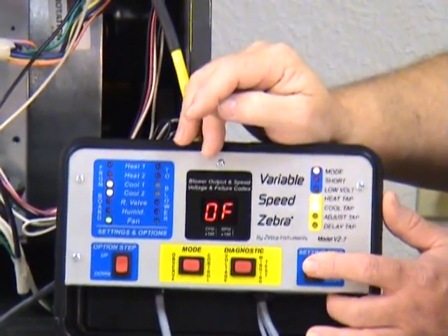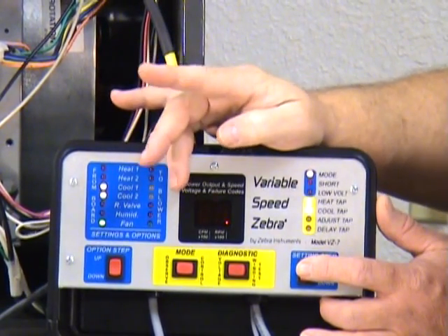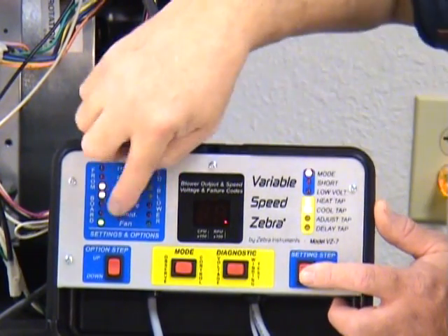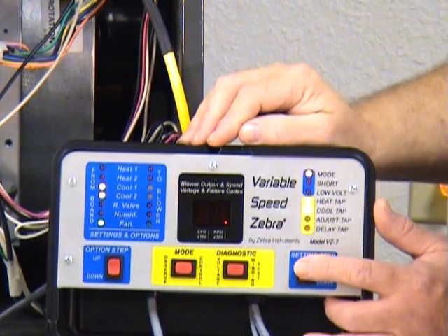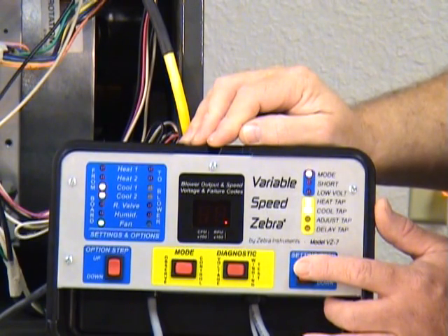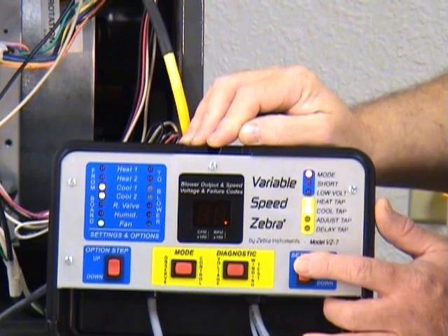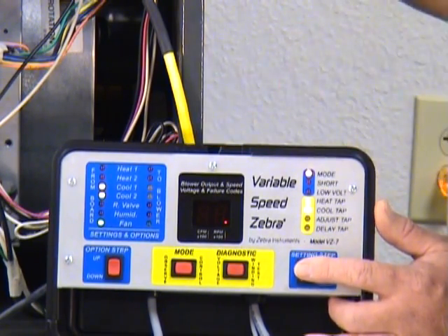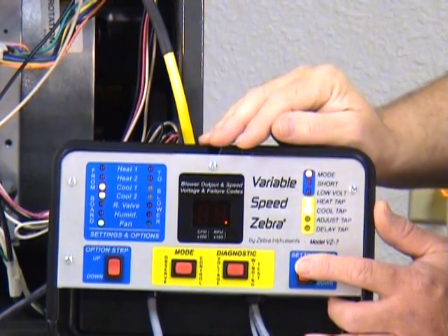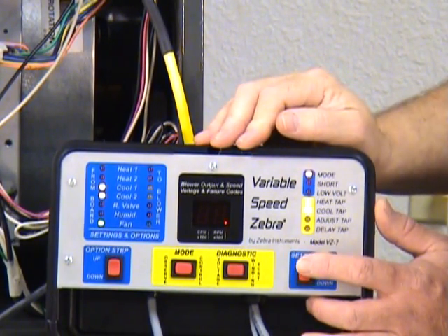If you run the small c or the small h, it will not turn the fan line on simultaneously, for those few systems that do use the command structure that way. Again, the vast majority of your motor manufacturers, your furnace manufacturers, are going to use both those commands at the same time, so you'd use the capital letters.